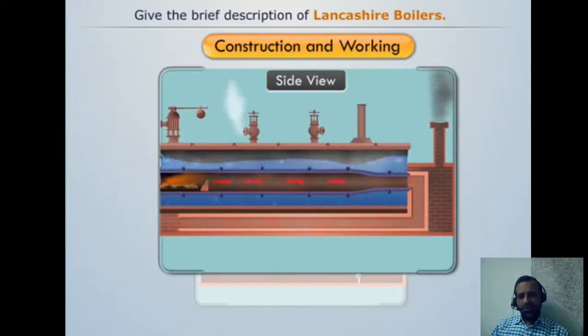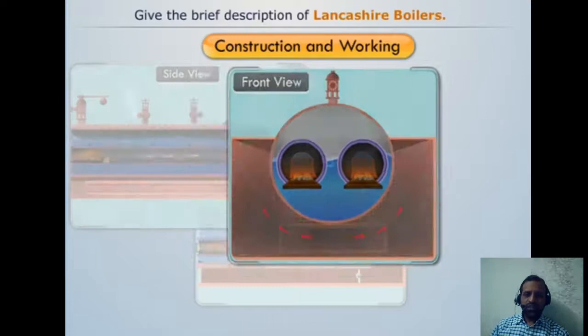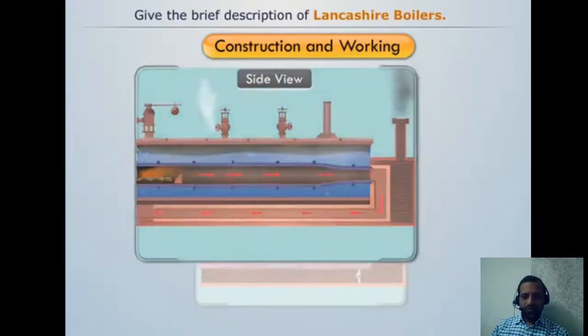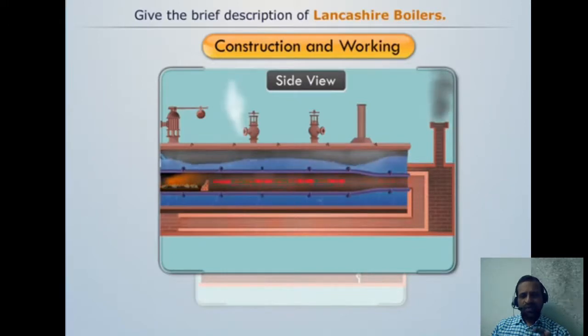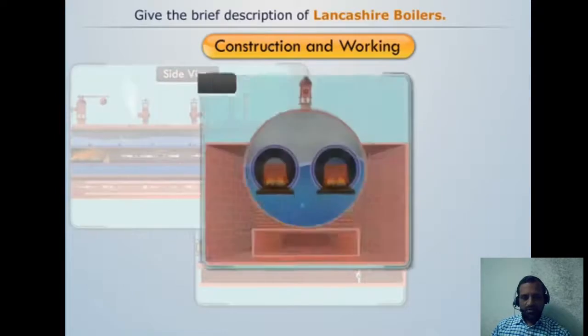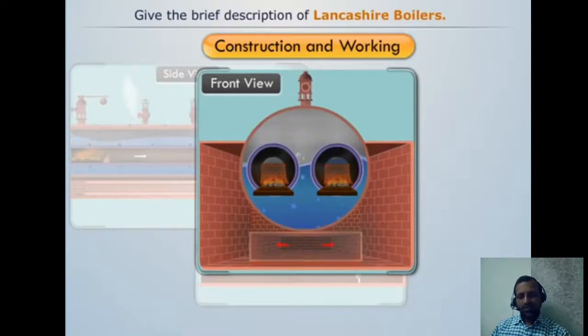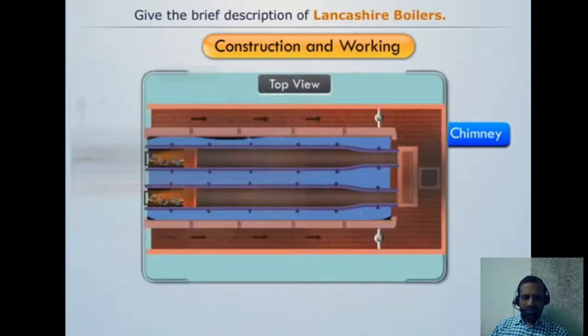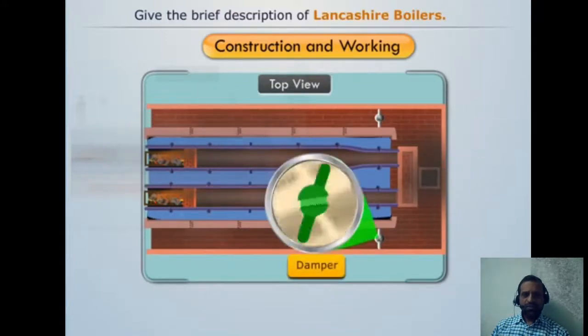In the side view, you see only one pipe, but there are definitely two fire tubes. In the front view you can see two circular fire tubes. In front of each fire tube there is a grate, on top of which coal is fed and fired. The flue gases flow inside the fire tubes, with water surrounding the tubes. A damper is provided to change the direction of flow of the flue gases.